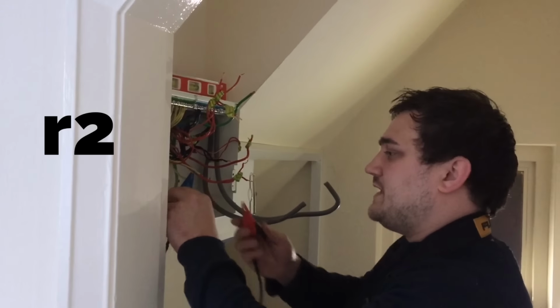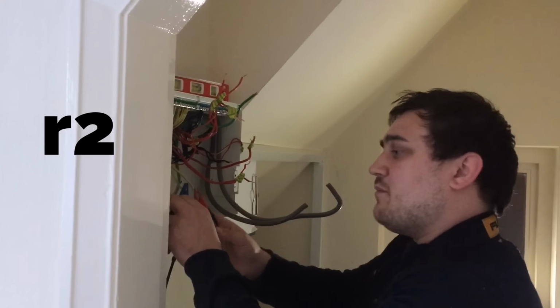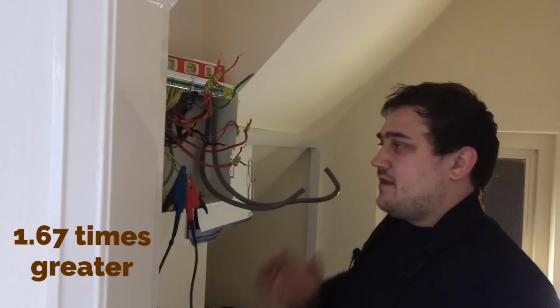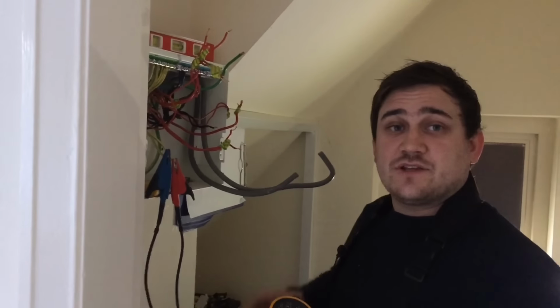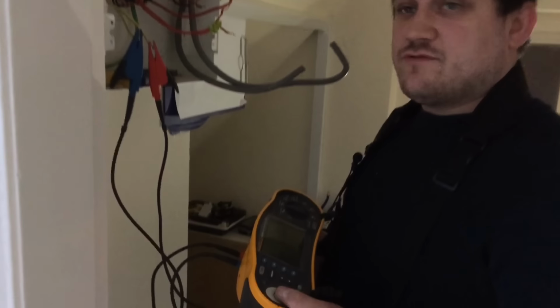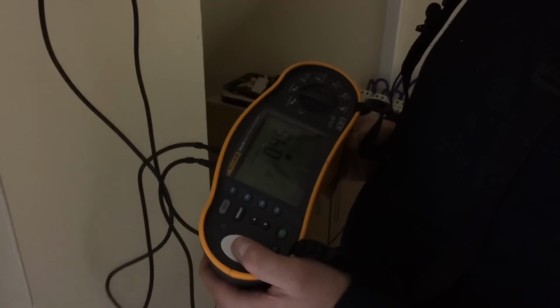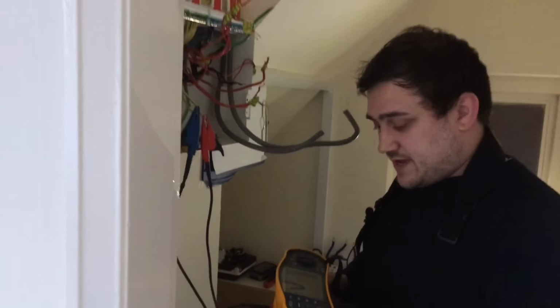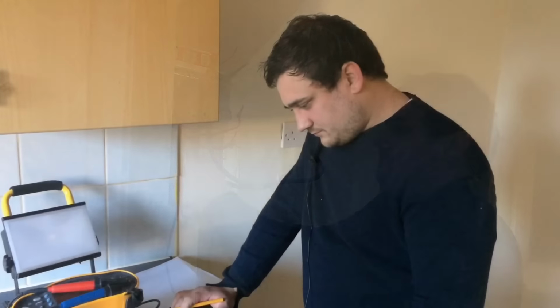Now I'm going to probe onto my CPC. This should be 1.67 times greater than the line and neutral conductors because it's a smaller size, therefore there's more resistance. And it is 0.45, which is around what we'd expect. So we're taking our end-to-end readings, little r1, little rn and little r2. Can you just explain to Marcus what you've done with those readings for me?